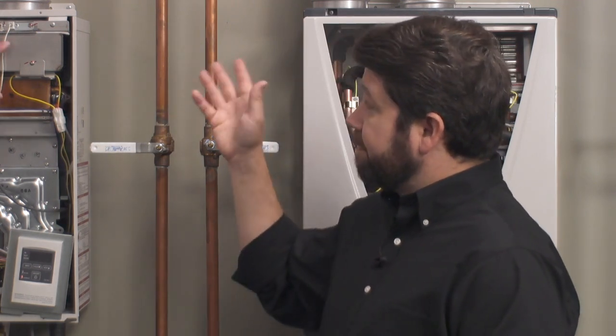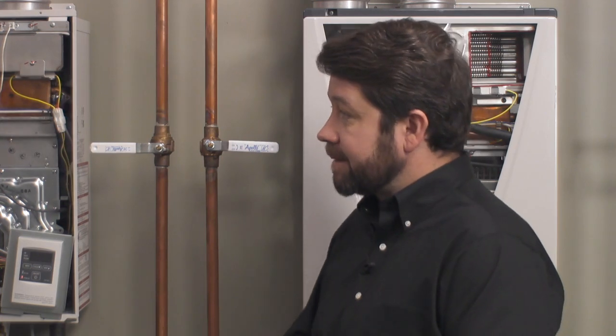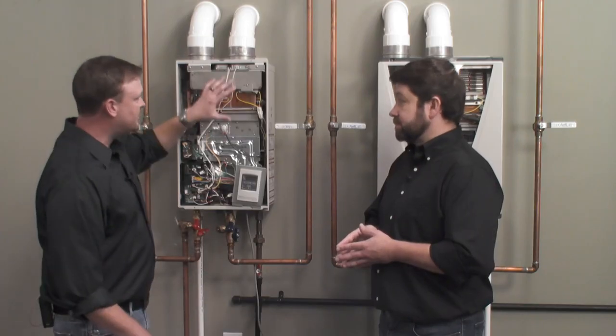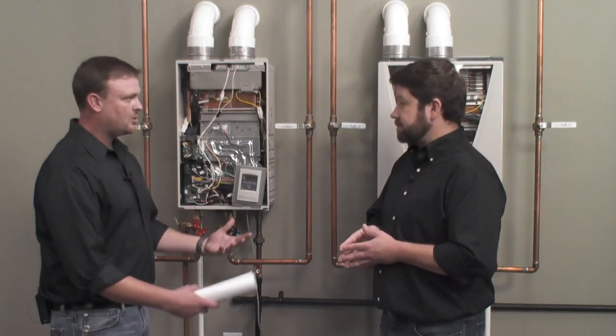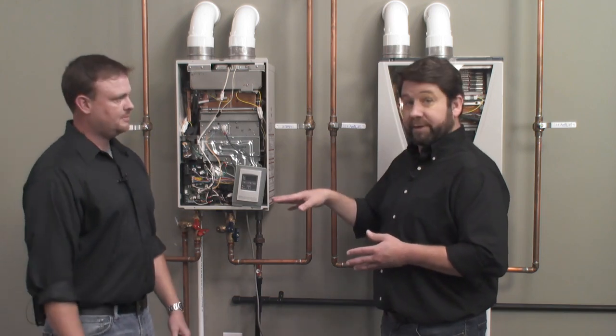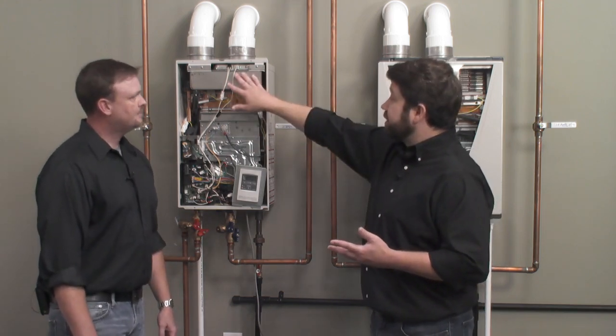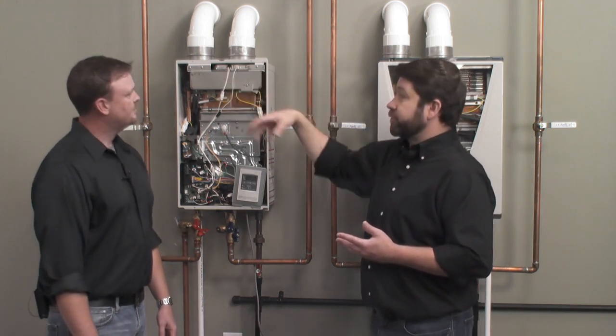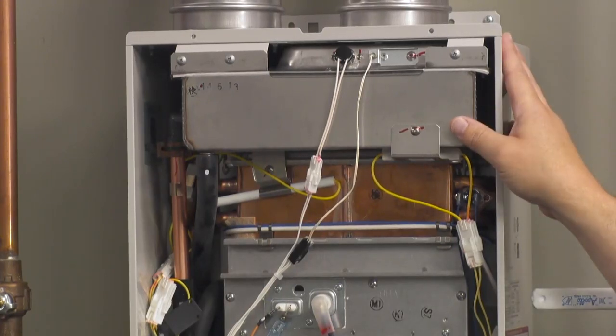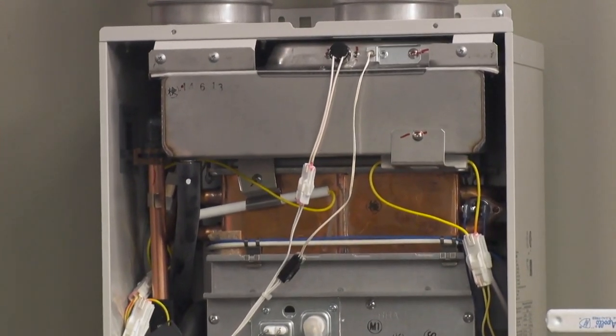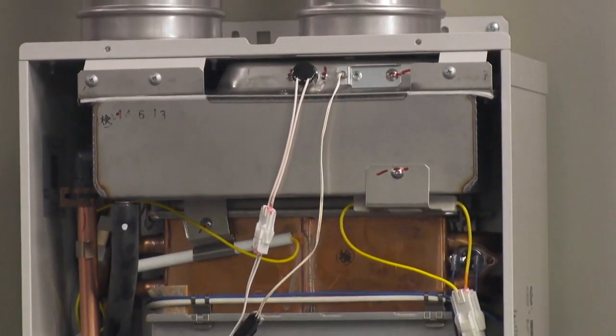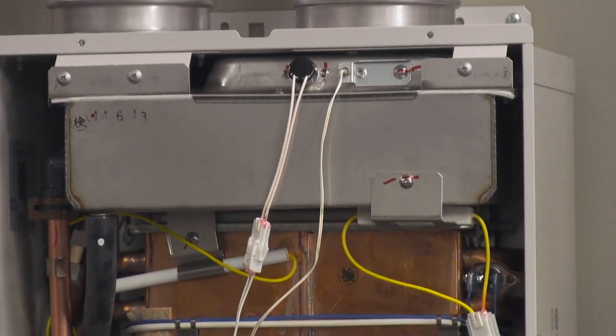Now, when we're using the PVC, we've got to keep those flue temperatures down. These dual safeties, that's part of their job. We've actually got several redundancies throughout the heater. This is a neat one. We've got a thermistor here that's measuring the temperature of those exhaust gases.